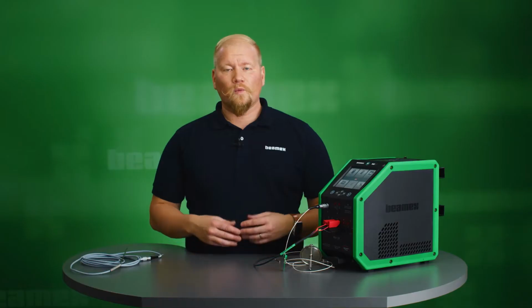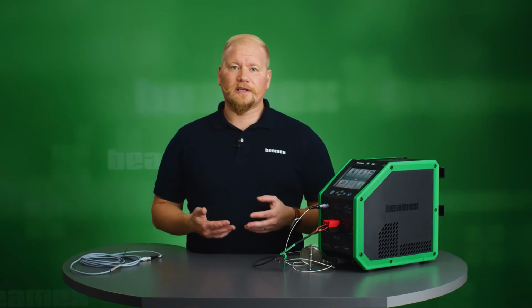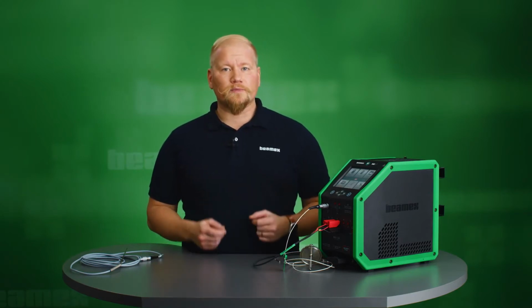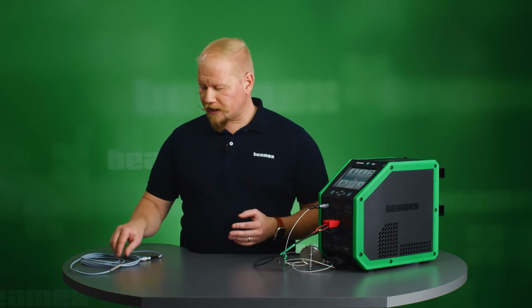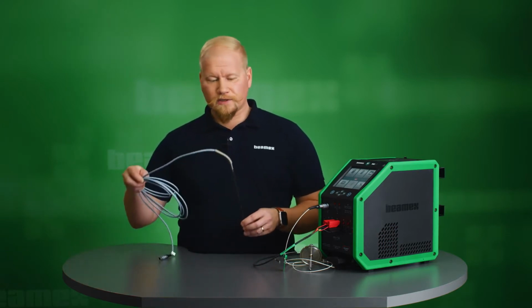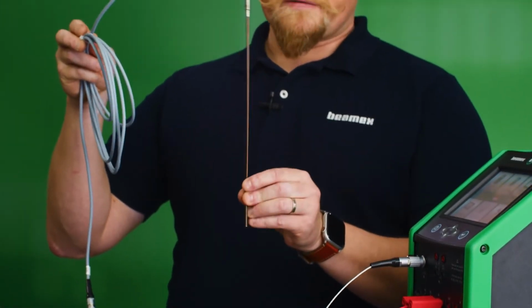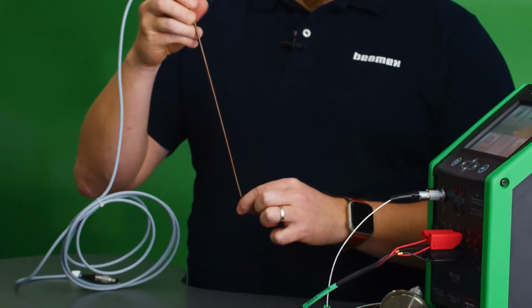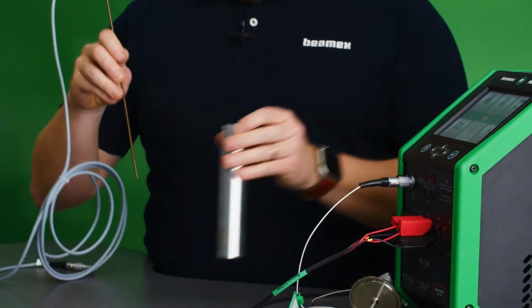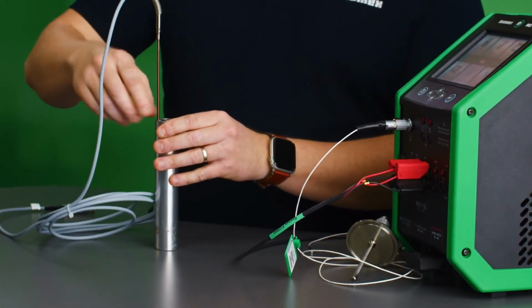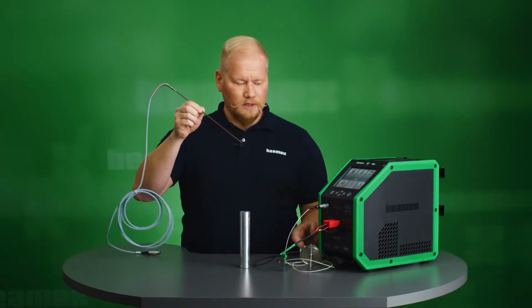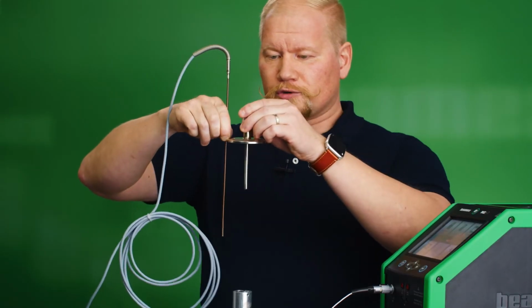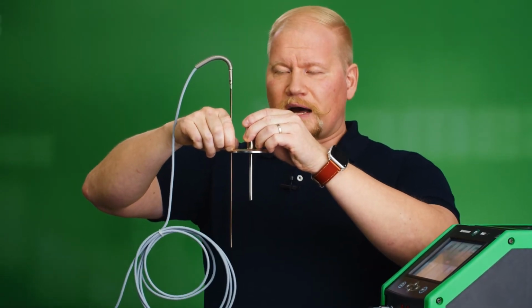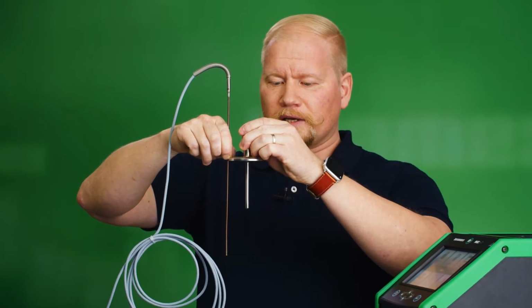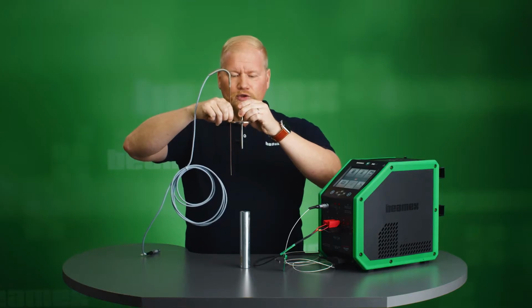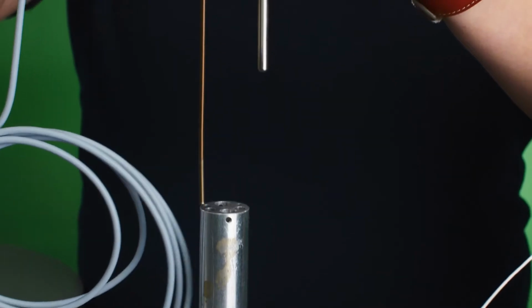When doing calibrations for short sanitary sensors, there are a few challenges that need to be overcome. If we start looking at them from the reference sensor point of view, here's one of my references. This model has a fairly long stem. And if I place it into my insert, I see that my immersion depth is about this much. Now if I compare it to my short sanitary sensor, the tips are on different levels. This means that they're not going to be able to measure correctly. There's too much uncertainty. I don't know what my result is really going to be.